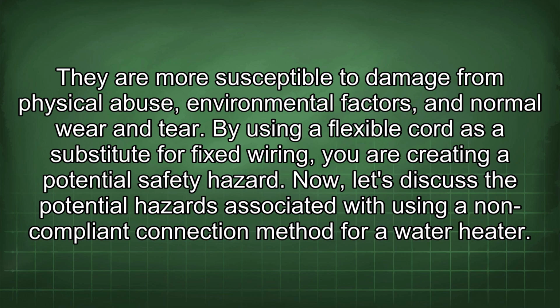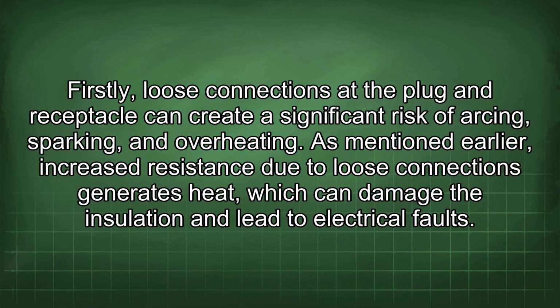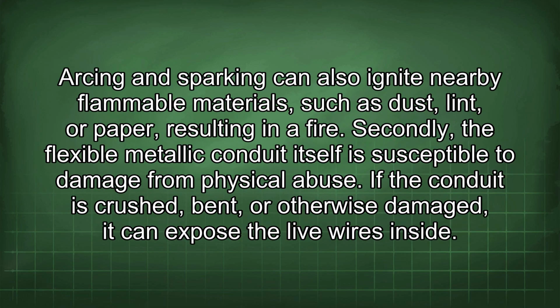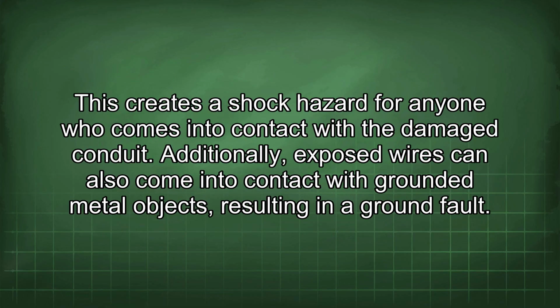Now let's discuss the potential hazards associated with using a non-compliant connection method for a water heater. Firstly, loose connections at the plug and receptacle can create a significant risk of arcing, sparking, and overheating. As mentioned earlier, increased resistance due to loose connections generates heat, which can damage the insulation and lead to electrical faults. Arcing and sparking can also ignite nearby flammable materials, such as dust, lint, or paper, resulting in a fire. Secondly, the flexible metallic conduit itself is susceptible to damage from physical abuse. If the conduit is crushed, bent, or otherwise damaged, it can expose the live wires inside. This creates a shock hazard for anyone who comes into contact with the damaged conduit. Additionally, exposed wires can also come into contact with grounded metal objects, resulting in a ground fault.